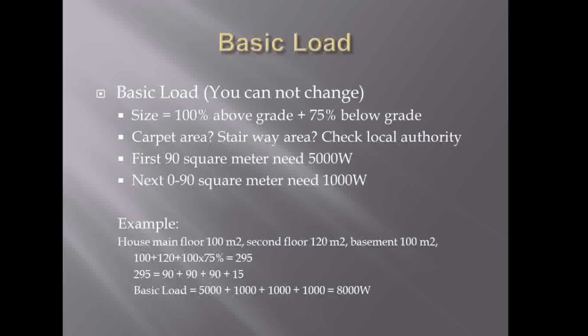For the basic load, you cannot change anything because it's purely based on what kind of property you have and the size of the property. When we calculate the size, we take 100% of the area above grade and 75% of the area below grade. Different authorities may define the area differently — air floor area or carpet area — and how stairway area is counted varies, so check with your local authority.